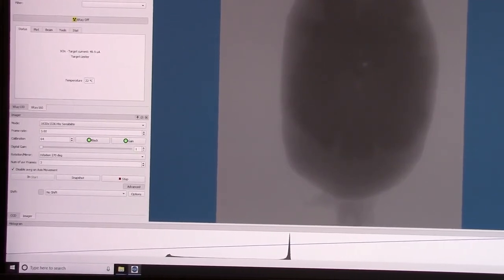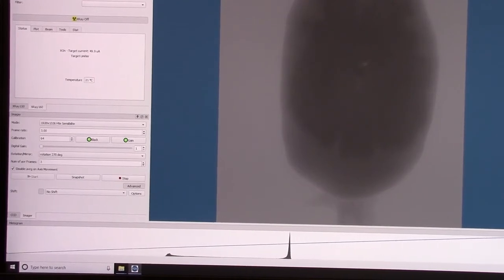One comment about the black and gain calibration is you do not necessarily have to do them at this point or do them manually. There are options where you can select some little toggle switches right before you start collecting your tomography data, and the system will go through the process for you. But it's important that you see at least once how to do it manually. And I think you will often find yourself using this, like if you're concerned that you exposed your detector to large over-intensity or something like that, then you're probably going to want to go back through and check your black and gain calibration.